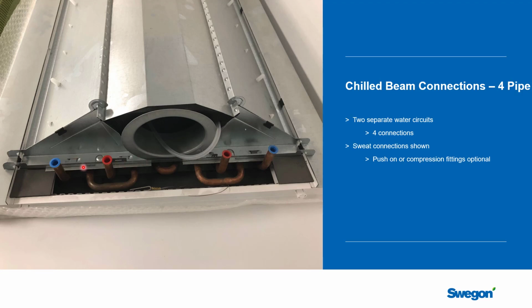About 2/3 of the tubes are dedicated to cooling and about 1/3 to heating. I also want to point out that these are just straight copper connections, so you could braze to these things, although you have to be incredibly careful not to cause any heat damage, especially to the finished surfaces. More likely you'd have some kind of push-on or compression fitting that would hook onto these coil connections.